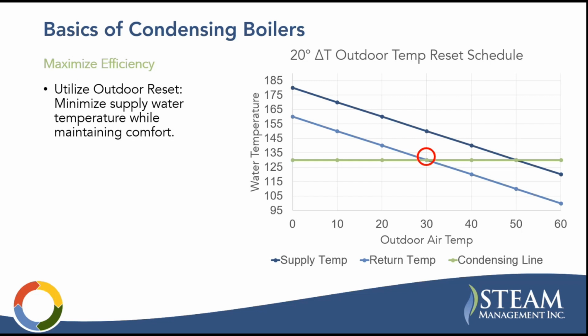At 0 degrees outdoor air temperature, let's say you need that full 180-degree set point like you've always been operating at to get the appropriate heat. You're not in condensing mode, but as the air temperature warms up, you continue to reduce your supply temperature set point to a point where that return temperature starts crossing this green condensing line threshold. And then for these outdoor air temperatures, you're in condensing mode and you're getting your mid-90s efficiency operating points.